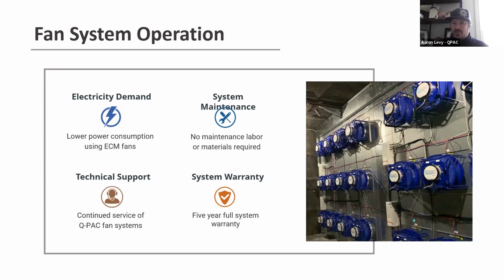And you've got big belt drive systems and big air handlers that they never really figured out how you're going to get that system out if it ever failed, and how to get a new one back in without having custom parts built. So this is a perfect example of how you can give an old air handler new life and extend it out by saving the customer not just money on the front side, but on the back side as well. Sometimes I've seen people just replace the coils in the air handler and the blower section and get another 10, 15 years of life out of these fans.